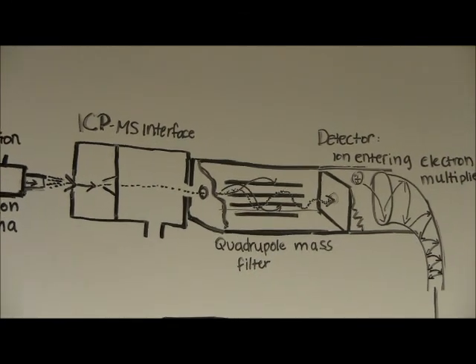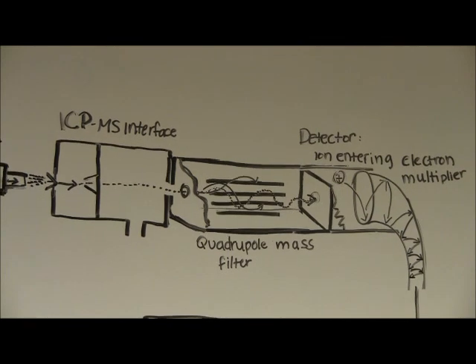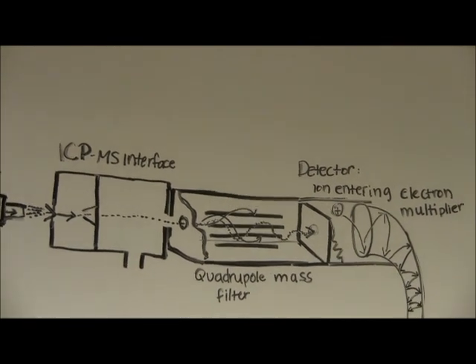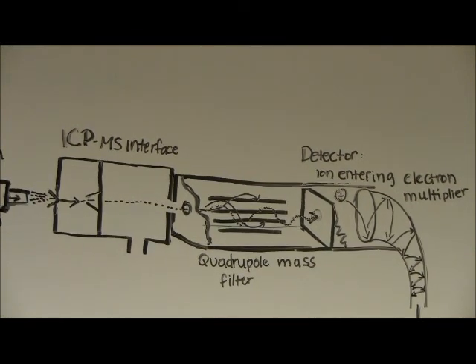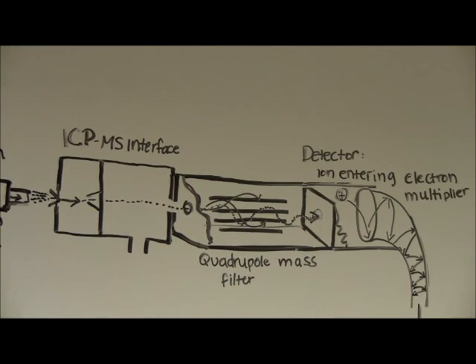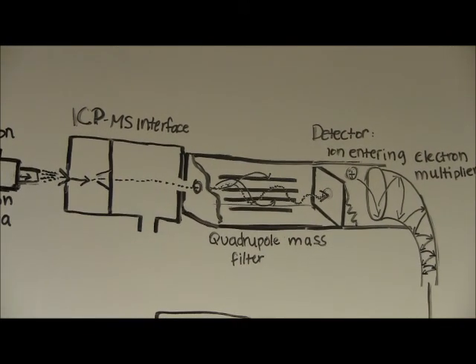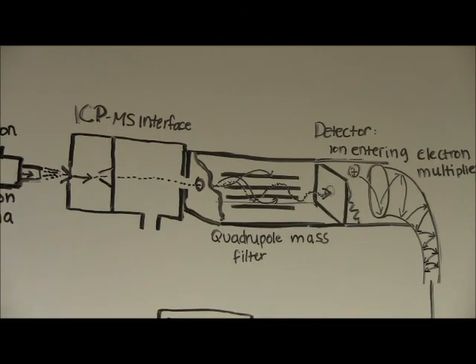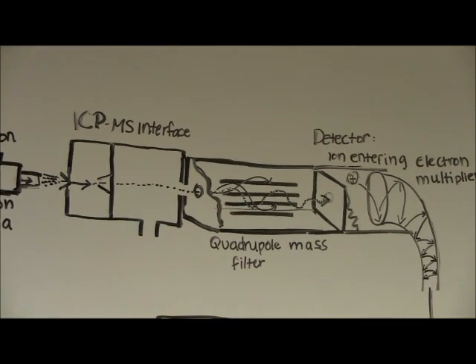The quadrupole mass filter is made up of four metal rods aligned in a parallel diamond pattern. A combined DC and AC electrical potential is applied to the rods with opposite rods having a net negative or positive potential. Ions enter into the path between all the rods. When the DC and AC voltages are set to a certain value, only one particular ion is able to continue on the path between the rods and the others are forced out of this path. This ion will have a specific mass-charge ratio. Many combinations of voltages are chosen which allow an array of different mass-charge ratio ions to be detected.